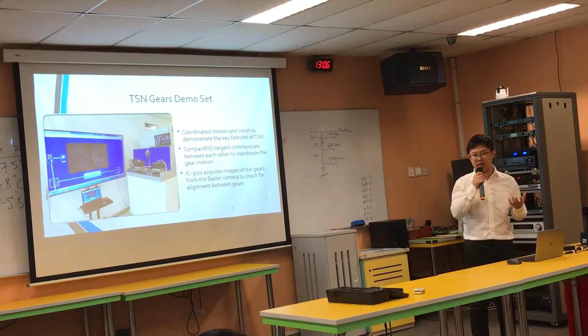So this is just an overview of the networks inside the demo set. How this works is there are 2 modes of gear control. One is UDP, one is TSN. In both modes, the position data of the master motor over here will be transferred over the network from the compact RIO to the slave compact RIO, and then used to control the slave motor. This ensures that the 2 gears are coordinated with each other and will represent our OT network in the demo set.